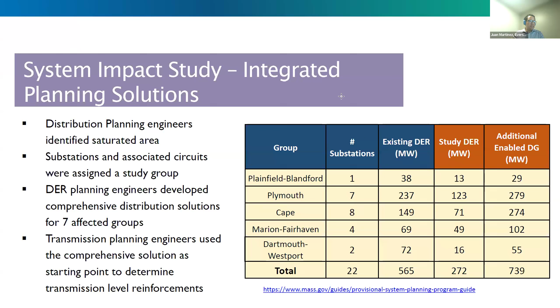The same analysis is completed for the distribution level, but for all of these studies, even at the substation level, we perform steady state stability analysis at the transmission level, short circuit analysis at both transmission and distribution level, and transient evaluation, EMT evaluation, at the distribution and transmission level for interconnection of all the DERs at both the substation and distribution level. Where some studies at other utilities are doing circuit level power flow and EMT, we had to step it up and do full EMT analysis at the substation level.